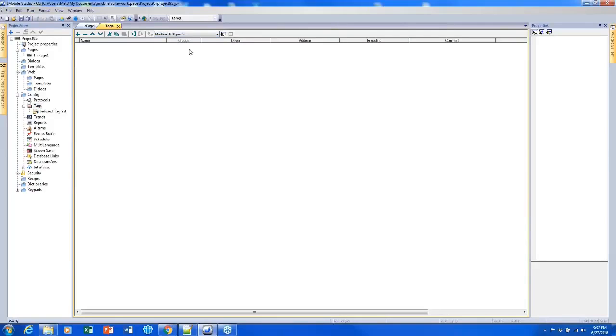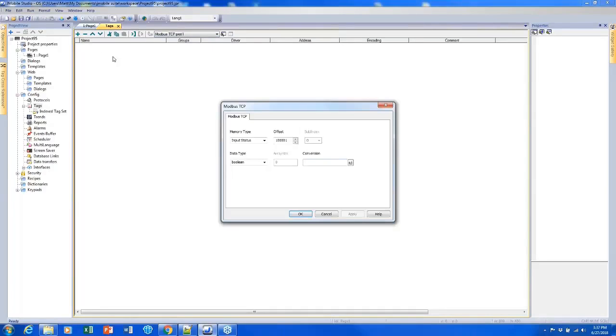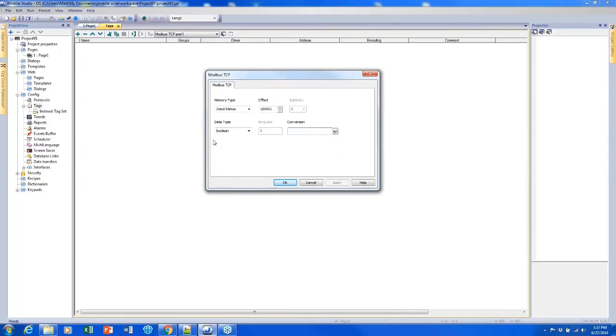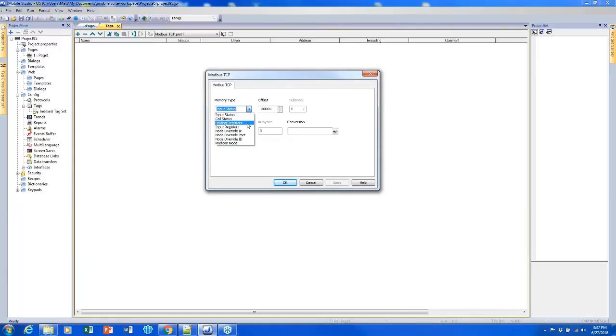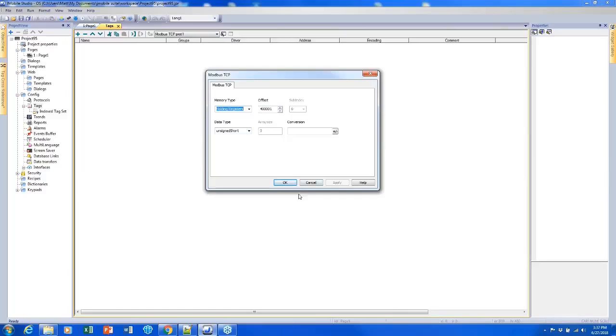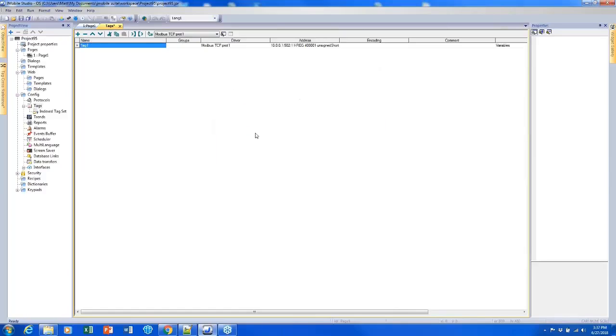I do want to start with Modbus TCP, so with that selected I can click the plus sign to create a new tag. When you create your first tag you'll have this dialog open up and you can configure the tags. I can select the memory type, the offset, and the data type which I'll just leave as an unsigned short.